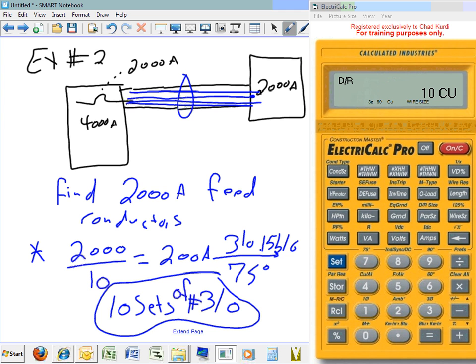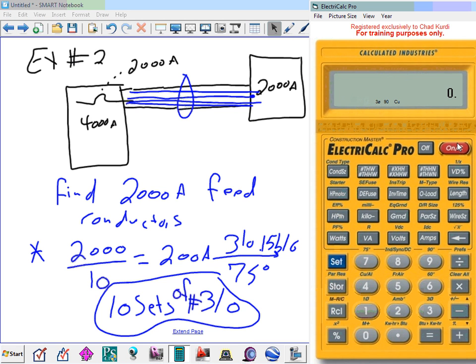Okay, let's go size the conductors. Make sure that we can get what we have based on my calculator. I want to remind you guys, we're going to reset everything. So set to 75. Before we start, Dustin, make sure it's 3-phase 75 copper. Okay, grab your load. What's my load? 2000 amp, right? And I need the wire size. So hit the wire size until you get... You can't find a conductor like this, so you need to parallel. What do you do when you parallel? I decided to put 10 of them. Hit 10 and then hit the term parallel. And what do you get? 3/0. Everybody got 3/0 from the calculator?